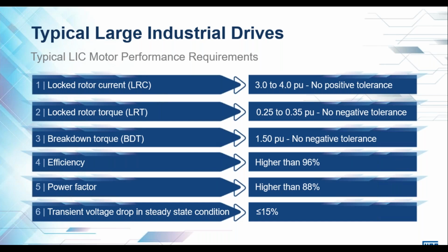The main reason for that is once you accelerate a machine and it gets to full speed, if you endure a voltage drop at the motor terminals in steady state conditions, it is the breakdown torque that gets used up in order to continue running without stalling. So the standards prescribe 10 to 15% voltage drop. The motor still needs to run the load. If we were to drop the breakdown torque to below 1.5 per unit, it would be very difficult to not stall during voltage drop conditions of more than 10 to 15%.